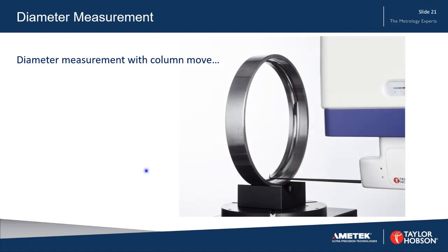And what we've done here is on this large bearing, we've measured near the center of the gauge range. We've taken a balanced trace at the bottom here, and the gauge is in its near zero position.